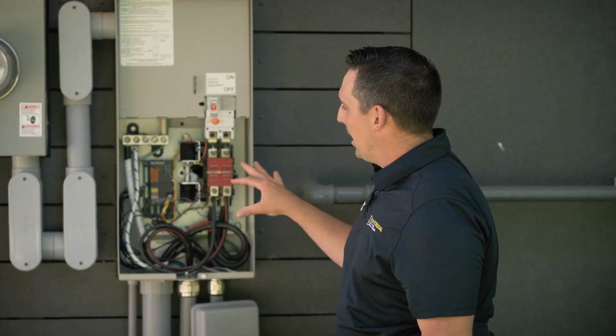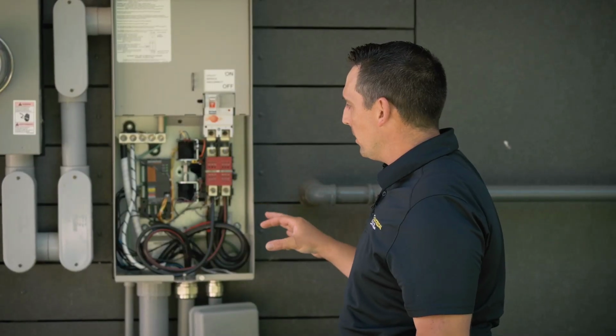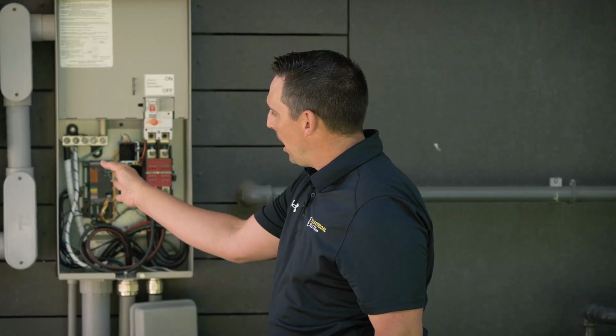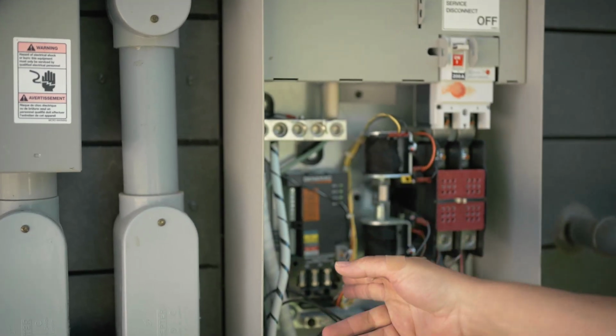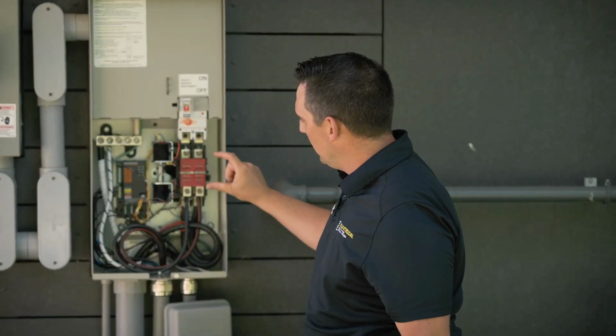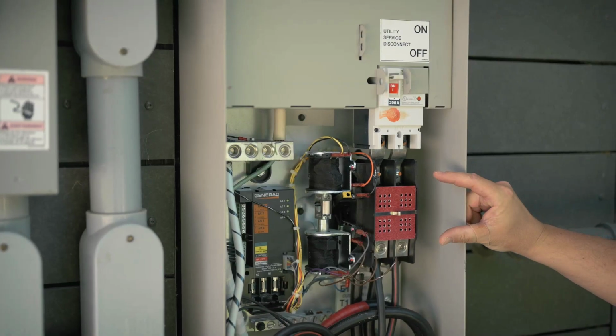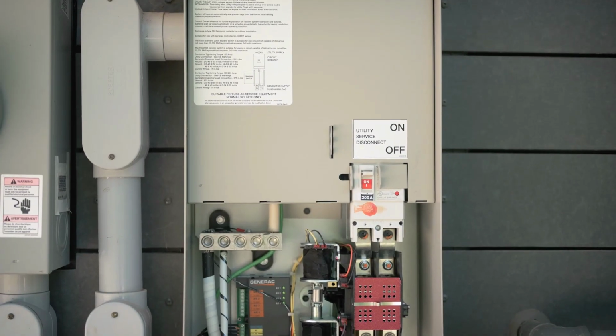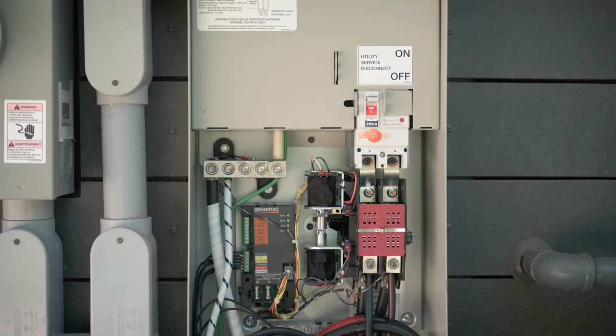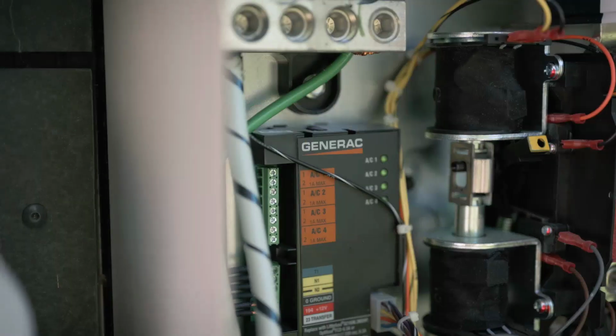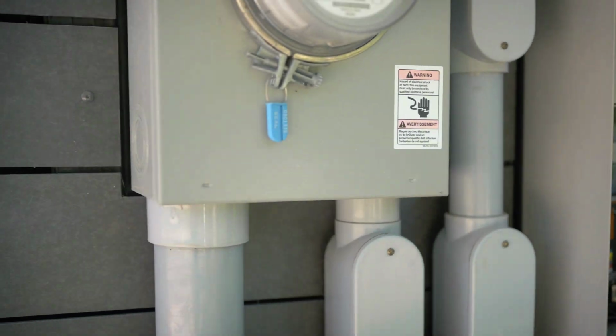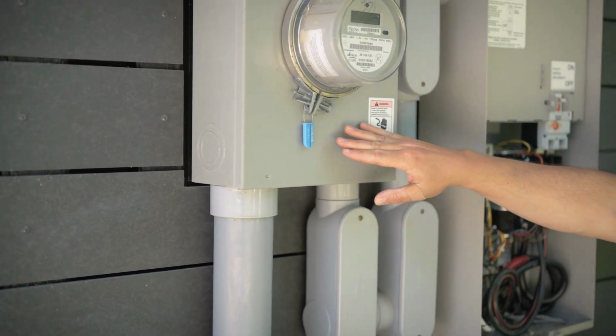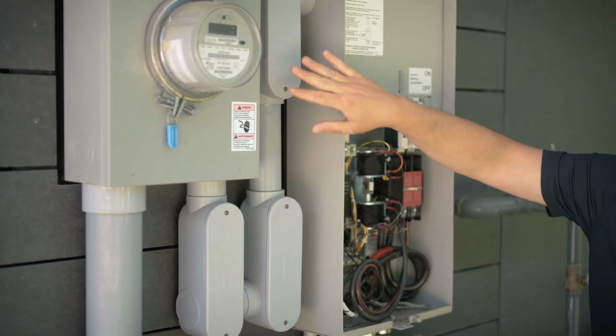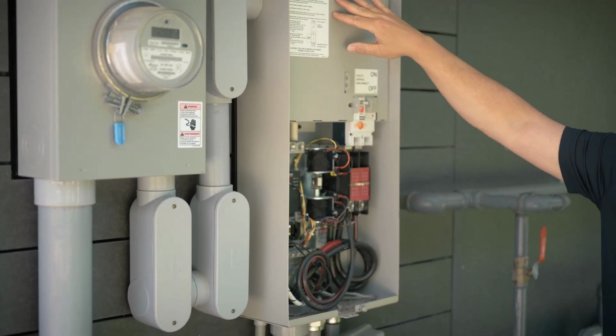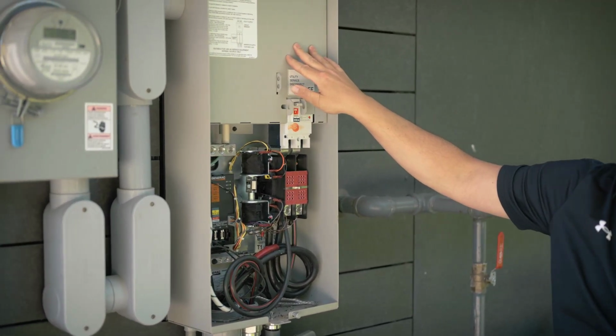So inside the transfer switch, there are several components. There is a control module known as a SACM, which is this module here. There's the transfer mechanism, which is this component right here, which is where the wiring connects. The utility power comes from the street, underground, into the meter, out of the meter, into the mains compartment, where the wires will connect to the circuit breaker.